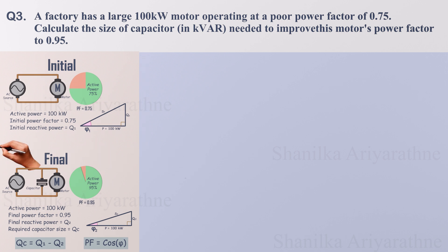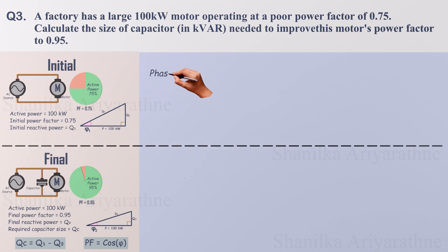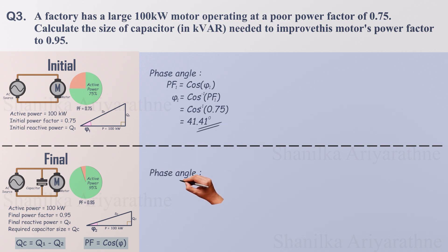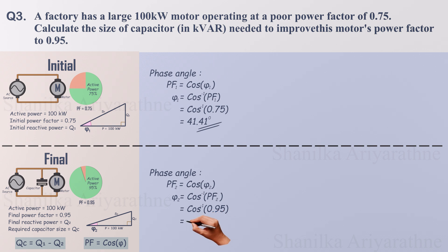Now let's start the calculations. First, let's calculate the phase angle phi1. It is 41.41 degrees. This angle represents the phase difference between voltage and current before correction. Now calculate phi2. It is equal to 18.19 degrees. This is the desired phase angle after correction.